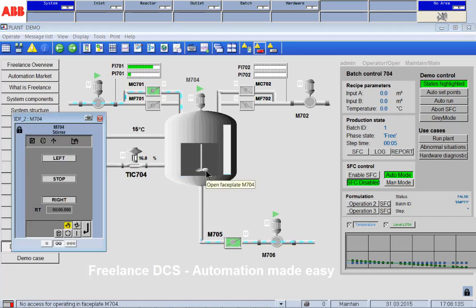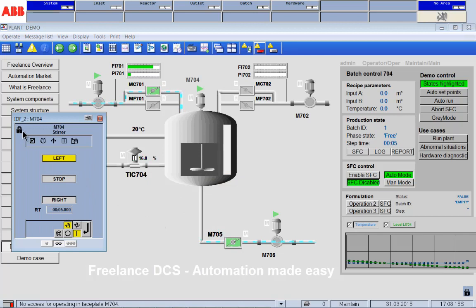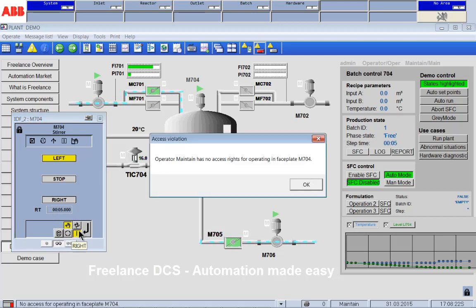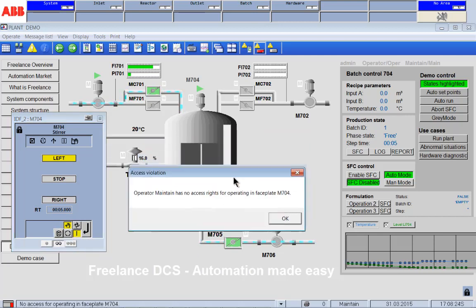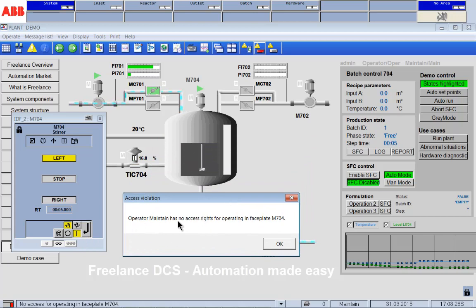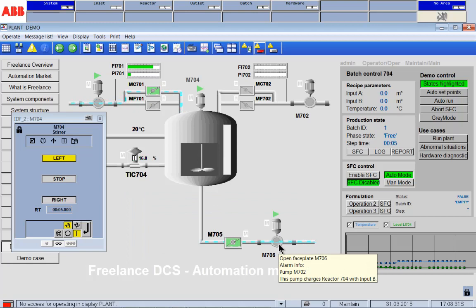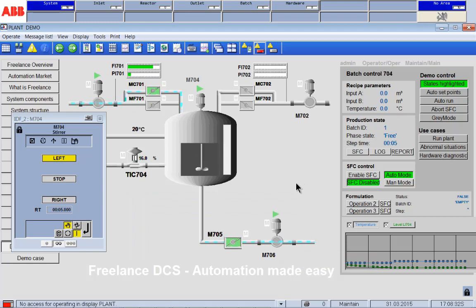If Mr. Maintain calls up a faceplate, the faceplate comes with a lock sign over here. That also means Mr. Maintain is not able to change, for instance, to stop the mixer. Operator Maintain has no access rights to operate in the faceplate. So you can specify tag by tag what the guy can do and what not.